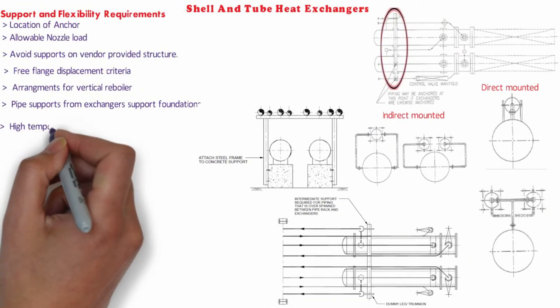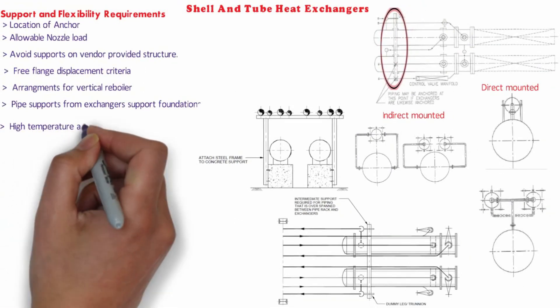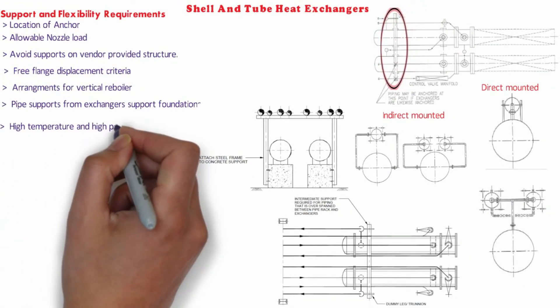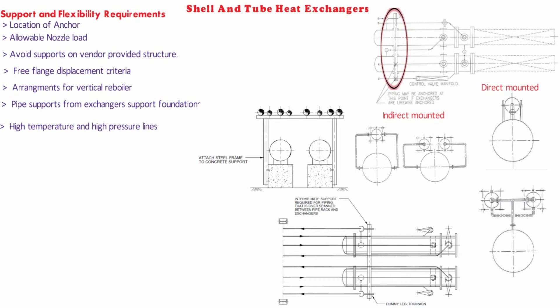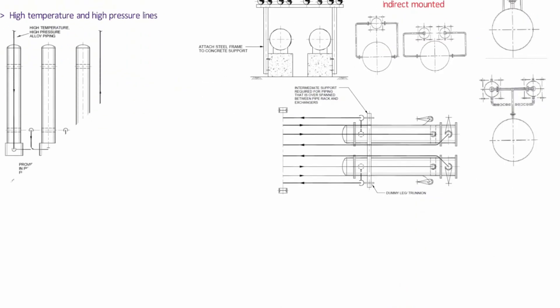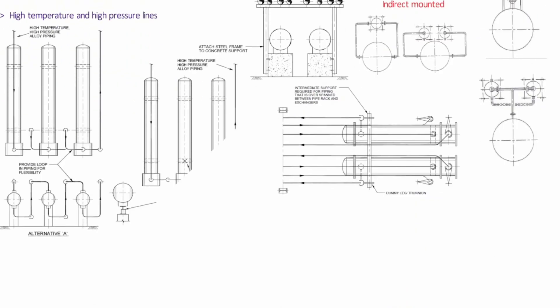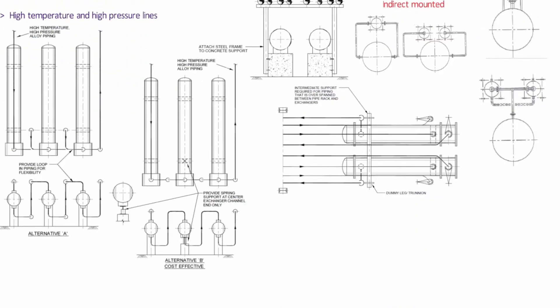Flexibility requirement for high temperature and high pressure lines. As shown in the pic, there can be two arrangements possible to ensure flexibility requirement for high pressure and temperature lines. First is to provide loops in the piping layout as shown in alternative A and other is to provide spring support on the central exchanger as shown in the alternative B.